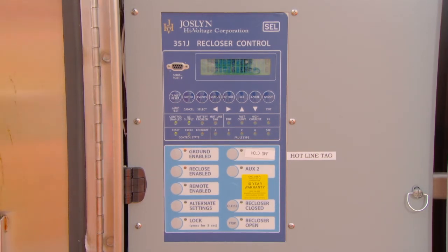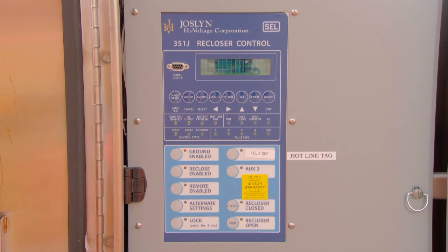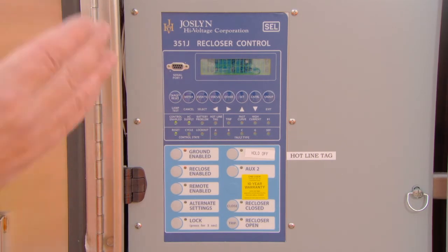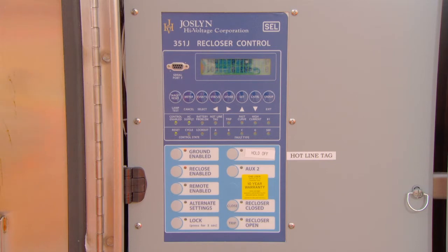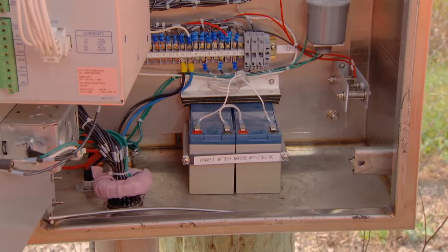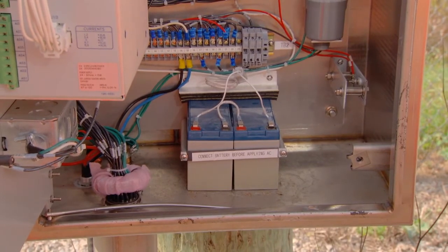For example, if this unit were 10 kilometers away from the station, the maximum fault current available at that location might be 2,000 amps, well within the threshold of this unit, allowing it to maintain that state for a longer time period. The maximum amperage rating for these units is 3,000 amps. If the unit were too close to the station, not having the high current setting on would affect its ability to trip to final lockout as quickly as possible and minimize any damage to the recloser. Setting the high current in the control will cause it to immediately lock out if the continuous current reached above the 3,000 amp threshold.